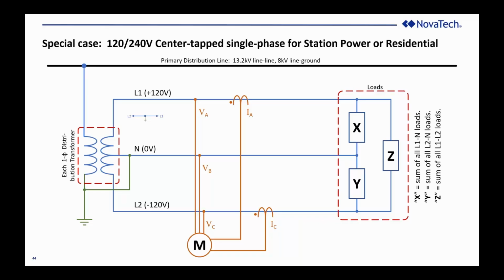So next I'm moving on to a special case of the 2-element wattmeter. Everybody should recognize here, without looking at the meter or the meter connections, what you see here is, if you care to think of it as a residential load, where I'm using a distribution transformer as the source, center tapped, maybe a 13.2 kV phase-to-phase, 8 kV line-to-ground distribution transformer with a 240-volt secondary with a center tap giving you 120 volts, with a 180-degree phase relationship between line 1 and line 2.